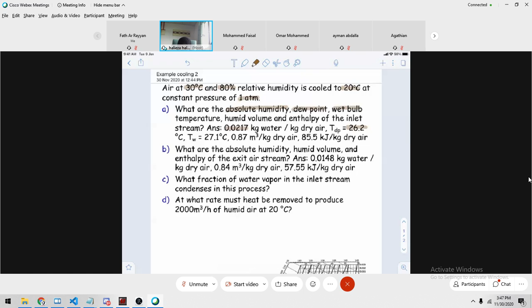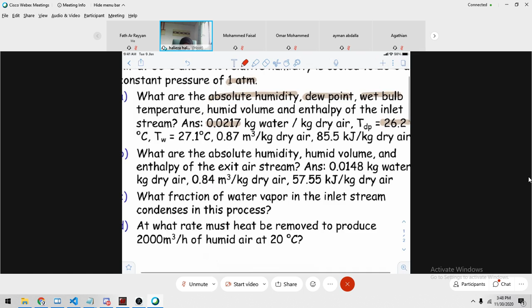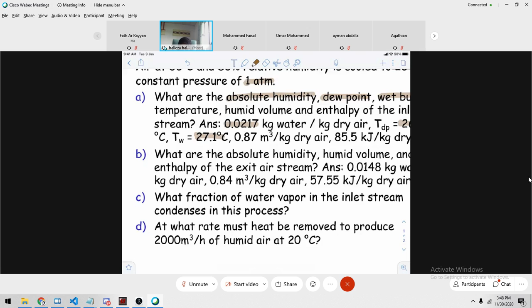How about getting the wet bulb temperature? How to get the wet bulb temperature? Draw a line toward the enthalpy line, the one with saturation dry air. The enthalpy scale, yeah. Okay, using the enthalpy line. So this is your point of interest. Draw a straight line towards that line, but not towards the scale. You stop at the 100%. So now your wet bulb temperature is 27, isn't it? Yep, 27.1. Well, that's okay, 27.